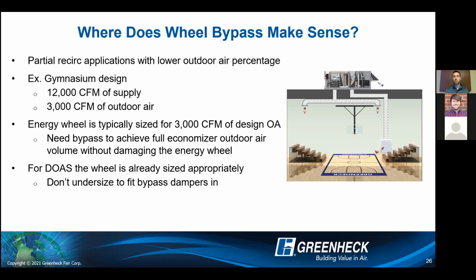During economizers, we'll open it up because that wheel is only sized for 3,000 CFM, and then we'll bypass the rest. But for the DOAS, the wheel's already sized appropriately. It's already sized for all the possible outdoor air that could come in. So we don't want to undersize the wheel to fit bypass dampers in. So hopefully that clears up where you would see wheel bypass from the RVE product line and maybe when you would want to specify it.